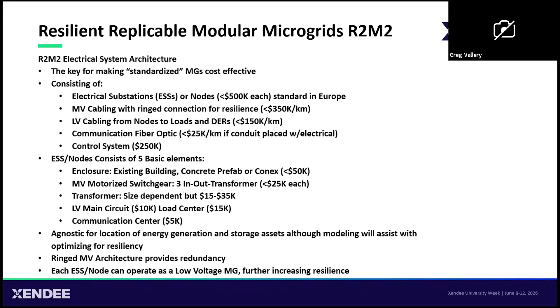So what it ends up doing is making a very agnostic system where you can plug and play with a variety of power pieces, if you want to call them that. We could have combined heat and power, it could become a central energy plant, but it could also be distributed energy loads around the buildings or at each one of these substations. Ultimately, the ringed medium voltage provides us redundancy so that if any one of the legs goes down, the power can be fed from the other direction. And each one of these nodes, if there are critical loads, we can make them operate as a low voltage microgrid as well.